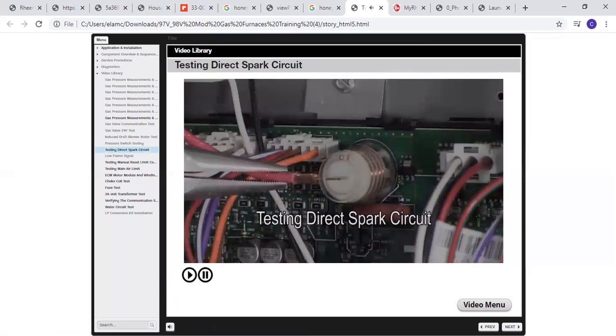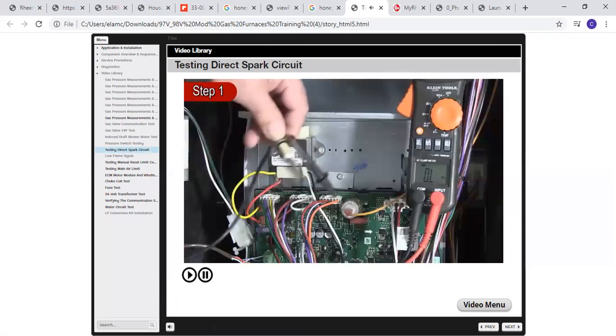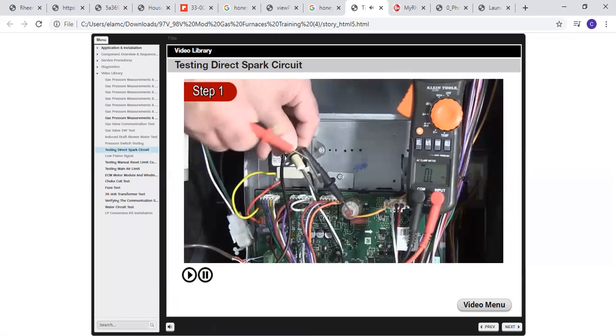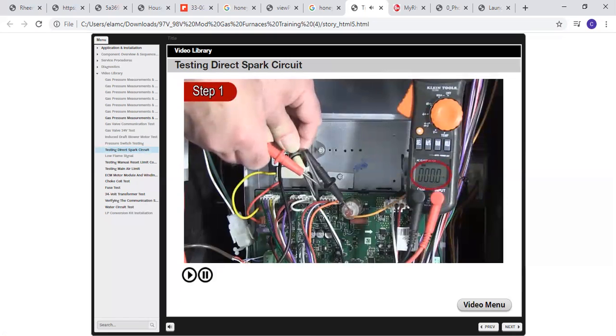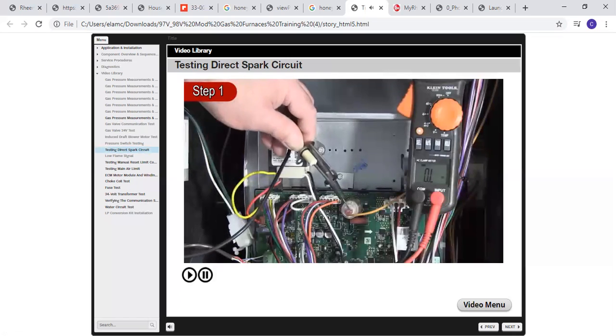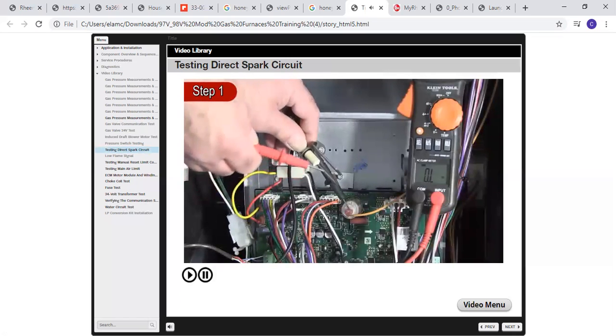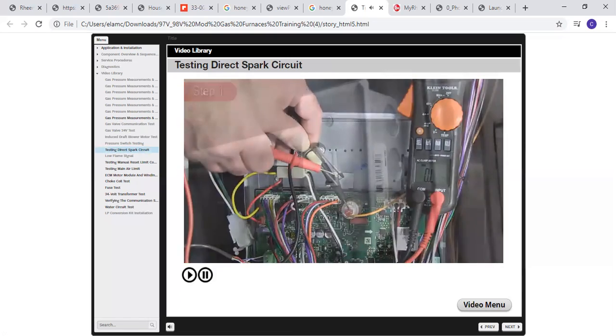Testing direct spark circuit. Step 1. Ohm out the spark igniter and wire assembly from the tip of the spark rod to the wiring connector that attaches to the furnace control board. The ohms should be 0 ohms. If the igniter ohms out infinite, replace the igniter assembly and wire. If the igniter assembly checks out okay, proceed to the next step.